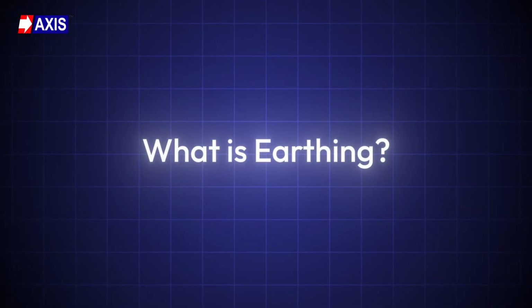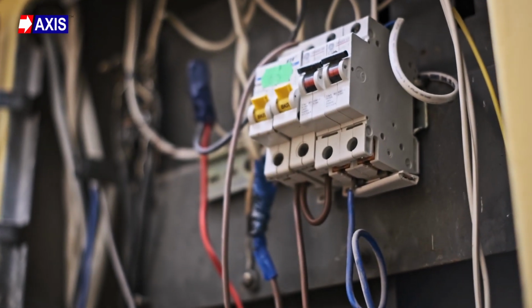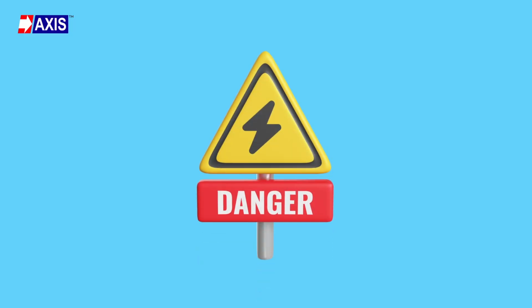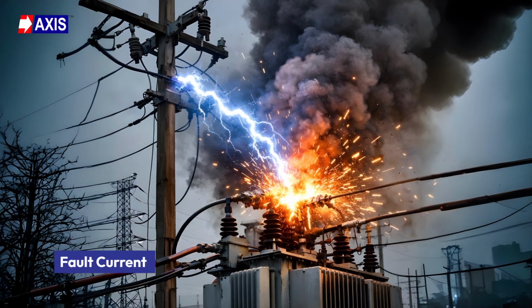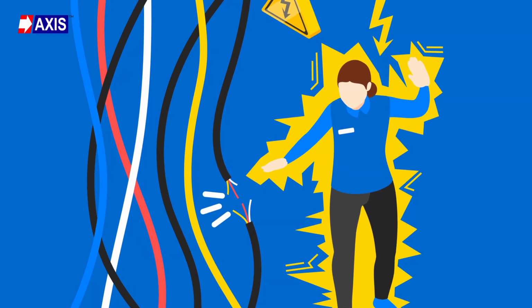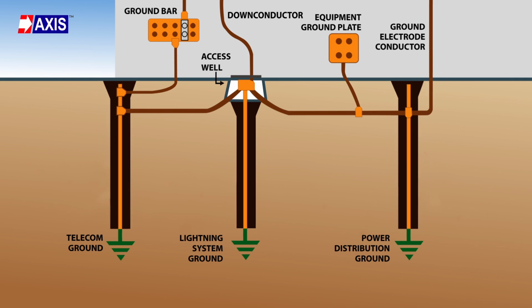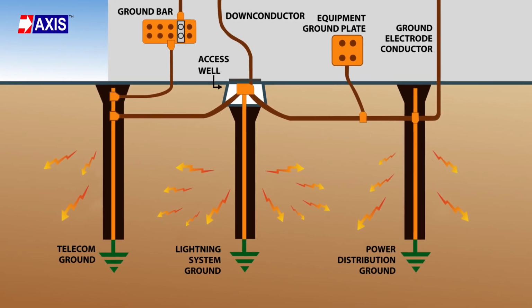What is earthing? In any electrical system, things can go wrong, wires can get damaged, insulation can crack, water can enter a switchboard, and many other things like that. But when this happens, electricity starts flowing where it should not. This unwanted flow is called a fault current. Fault current is dangerous because it collects on metal parts like panels, appliances, poles, cable armor, etc. And anyone touching these parts will get an electric shock. Earthing solves this problem by giving the fault current a low resistance path into the soil so that it returns to the source to protect human life and equipment.